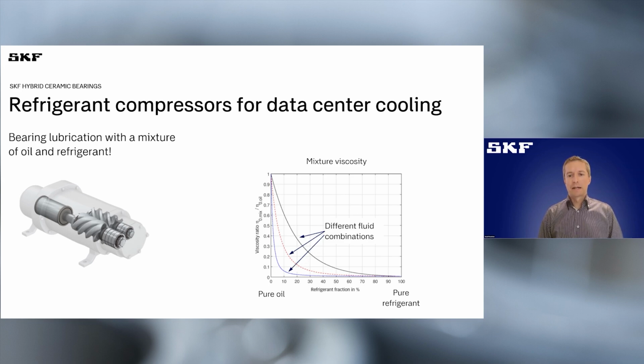But this transition from a pure oil to a pure refrigerant is not linear. Your viscosity actually will drop much faster than the percentage of increase of dilution in your application. Traditionally here we were facing maybe dilution values of 10 to 20% in air conditioning applications, but now moving to higher temperatures and also due to the introduction of new refrigerants, we are facing values of dilution going up to 30% or even beyond.